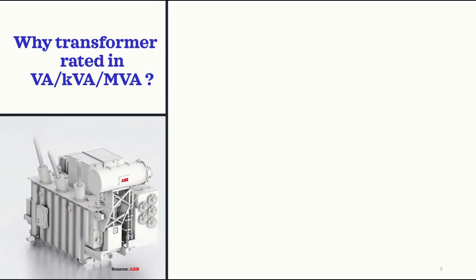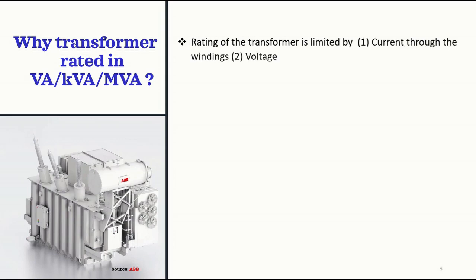The main reason is that the capacity of a transformer is limited by two factors. The first one is the current that the transformer winding can carry, and the second one is the voltage that the transformer is designed to work without saturation.